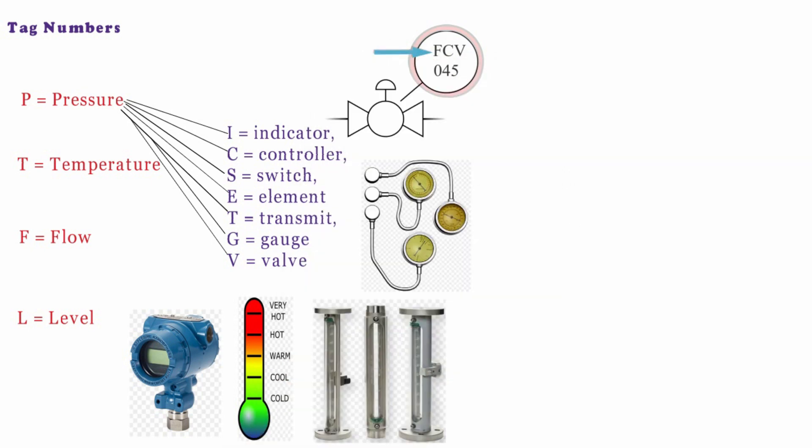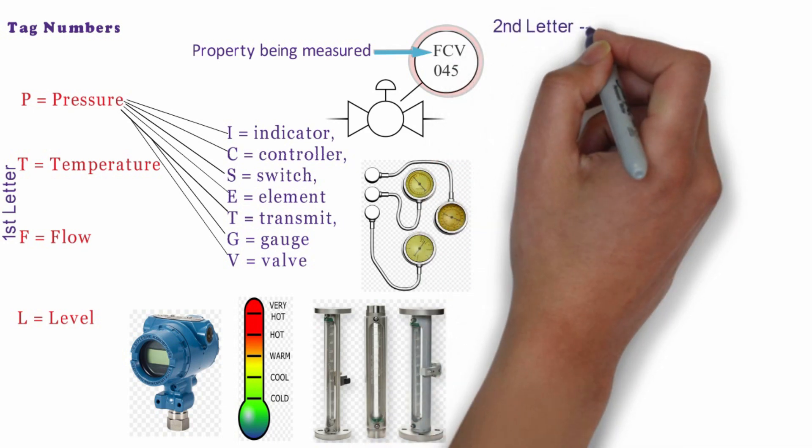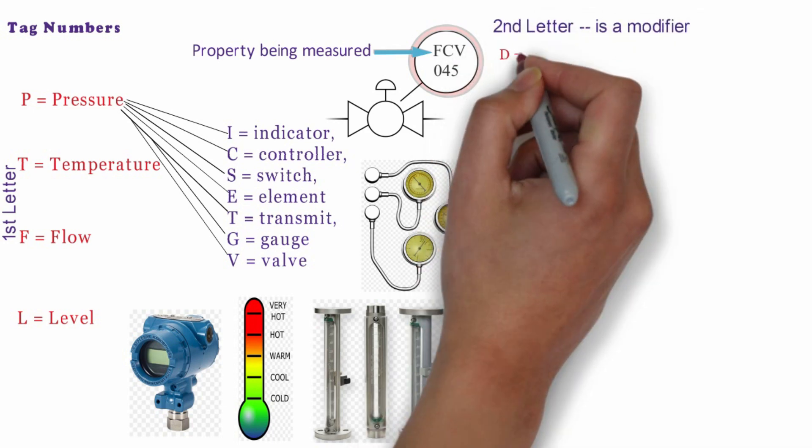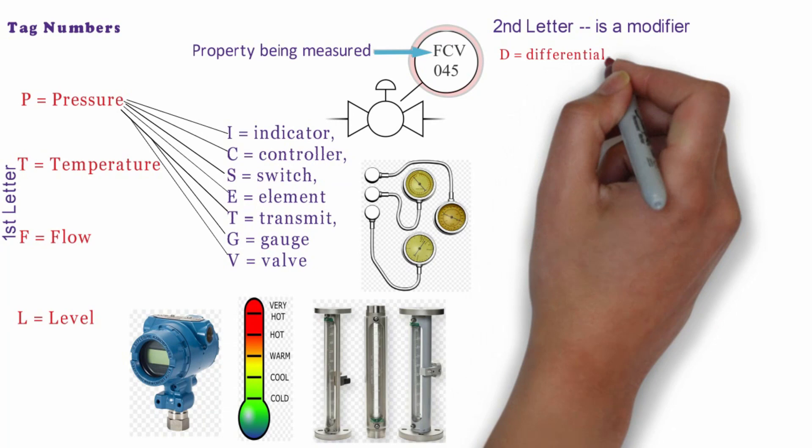The instruments are identified up to five letters. Two are a minimum. First letter is the property being measured like flow rate, pressure, temperature and level. Second letter is a modifier like D is for differential and F is for ratio.